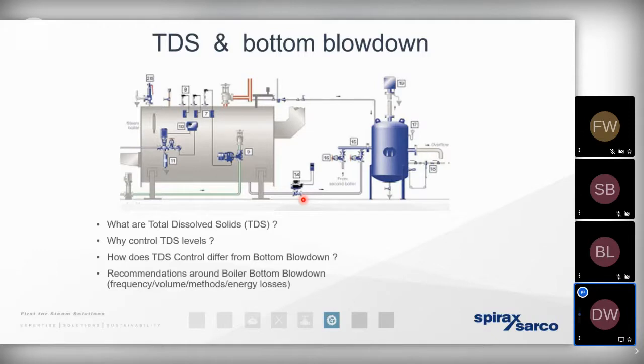And then we've got what we refer to as the TDS, or total dissolved solids. So that comes back to the analogy of the sugar that I was speaking about. As we start to evaporate the water, the chemicals that are present within the water in the boiler become more and more concentrated. And if they're left unchecked, if it were to reach a dangerously high level of concentration, we'd get a lot of foaming present in the boiler. And that can be an indication that there's a buildup of scale and insulation on the heat transfer surface areas. It can also make it very difficult for the level control probes to determine the true water level. But as we get a fluctuation in pressure, we can draw out that foam into the distribution pipework. It's going to be very wet and sticky, and it can also result in a little bit of erosion to sensitive areas.